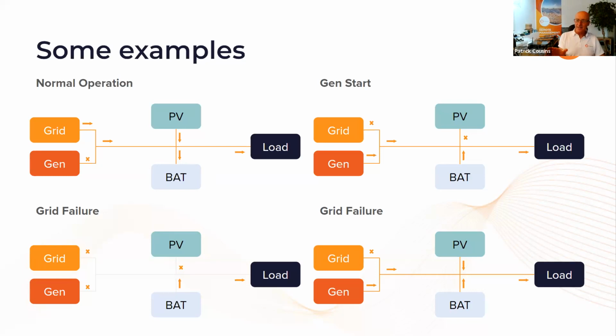Ideally in this case you do not need your generator at all, because the battery PV system is big enough, and because you were aware or thought maybe a power failure was going to happen, so you've got enough state of charge in your battery. But if you get a sudden power failure at 7 a.m. when you're expecting the sun to come up and it hasn't yet. Then you might run into trouble, so you have to decide what's the priority. This is just an example of all 8 of the different stages of 2 particular scenarios.